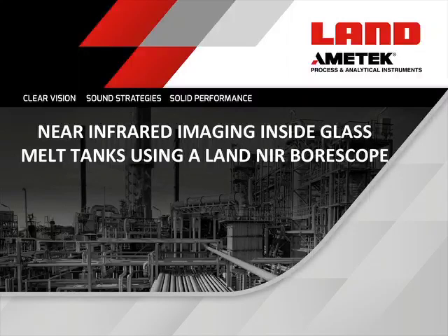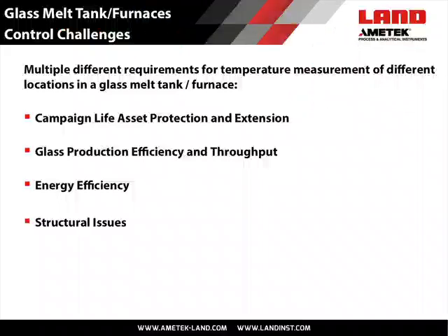Good morning. Today I'm going to talk about the Land NIRB borescope thermal imager and its use in the glass industry for measurements in the glass melt tank. There are many needs for accurate temperature measurement and imaging within the glass melt tank. For instance, campaign life extension. Critical refractory surfaces such as those around the port arches are continuously monitored. Crown temperatures are long-term temperature trended. This allows optimization of reversal times and longer refractory life can be achieved.